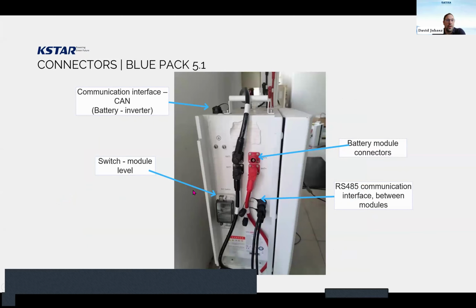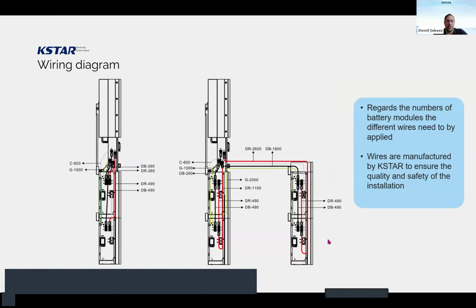If we check one module, it has a CAN communication interface on the top, which is responsible for the communication between the battery and the inverter. It has a switch lever on the left side of the battery pack. This is responsible for disconnecting the packs from each other. The battery module connections are there, and the RS485 communication interface between the modules. We are prefabricating the cables depending on the chosen topology of the system.